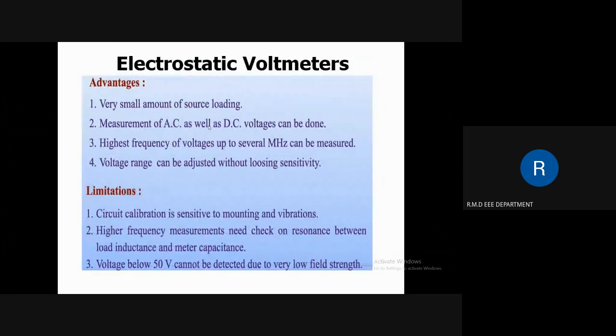Now, the advantages of this electrostatic voltmeter. It has a very low loading effect, as only electric fields have to be built up. The voltage source loading is limited to the reactive power necessary to charge the system capacitance, and voltages up to 600 kilovolts can be measured. If there is high pressure or vacuum between the electrodes, it provides very high resistivity, therefore the active power losses are negligibly small.